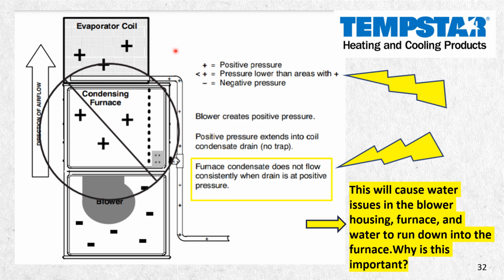If you do have to put the cap on it, drill a hole through it at the cap, or you come in with a bigger reducer bell here, like say a 2-inch down to 3/4, and then just let that drop down into that 2-inch and kind of do that. But a furnace condensate does not flow consistently when the drain is at positive pressure. This will cause water issues in the blower motor.